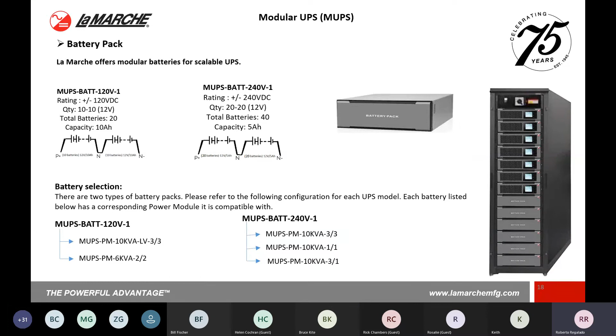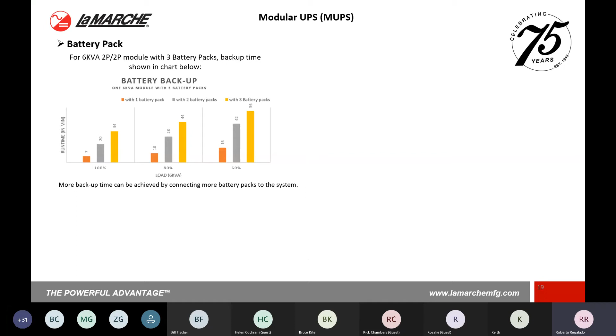I won't go through all the battery runtimes, just a quick example of a typical runtime or battery backup using the 6 kVA split phase to split phase module with 3 battery packs, showing some backup times. We updated our data sheet since last week's email, so it should now be on the website showing DC current draws for each power module, in case you need to configure a certain number of battery packs or an external battery.